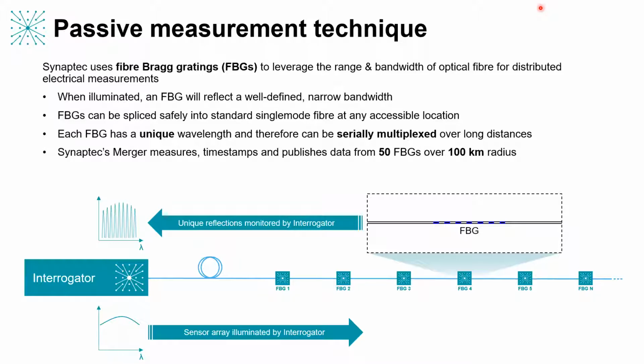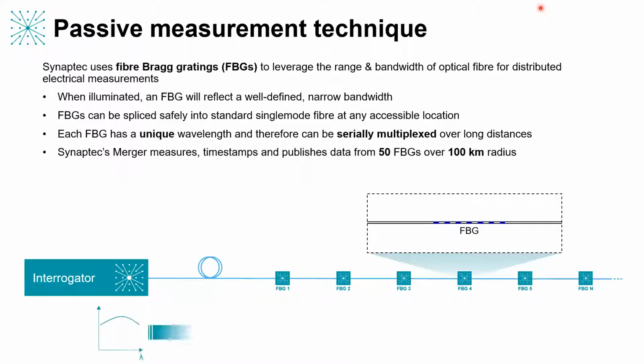So that's the fundamental platform that we use in order to get at a measurement of strain or temperature at those locations. FBGs are low-cost devices. They've been around for 30 years. They're really commonly used in structural health monitoring applications. Because they're based on wavelength, the multiplexing of them is very simple. We can put 50 of them in one fiber. Each of those have a different color of light, and so they're each transparent to one another, which means that at the interrogator in a substation we can see all 50 of them simultaneously, and the bandwidth that we've got on our measurement is limited by how fast we want to sample at that central location.